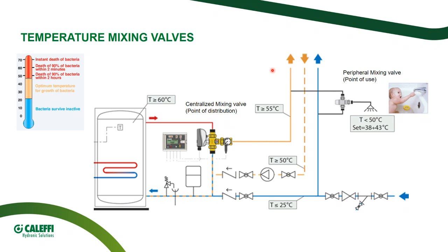Think about a leakage of a gate valve or a ball valve in the false ceiling dripping at 65 degrees. It can be a very great issue, especially in a hospital where maybe you can have children or weak people or elderly people, and think about also the maintenance of some components that are managing water at 60, at 65, and also to take into account the thermal losses, so the energy bills at the end of the month.